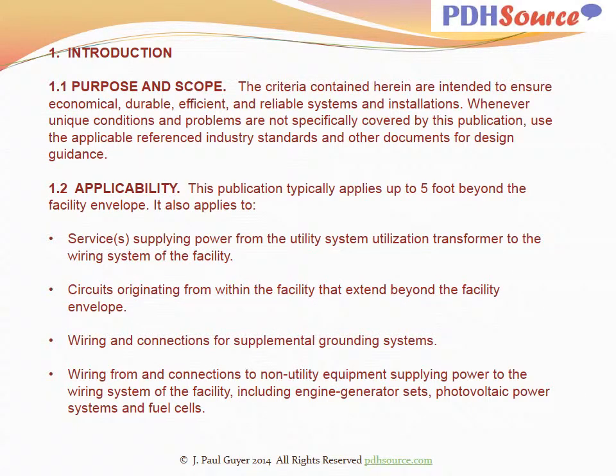The criteria contained here are intended to ensure economical, durable, efficient, and reliable systems and installations. Whenever unique conditions and problems are not specifically covered by this discussion, use the applicable referenced industry standards and other documents for design guidance. This publication typically applies up to 5 feet beyond the facility envelope. It also applies to services supplying power from the utility system utilization transformer to the wiring system of the facility, circuits originating from the facility that extend beyond the facility envelope, wiring and connections for supplemental grounding systems, and wiring from and connections to non-utility equipment supplying power to the wiring system of the facility, including engine generator sets, photovoltaic power systems, and fuel cells.